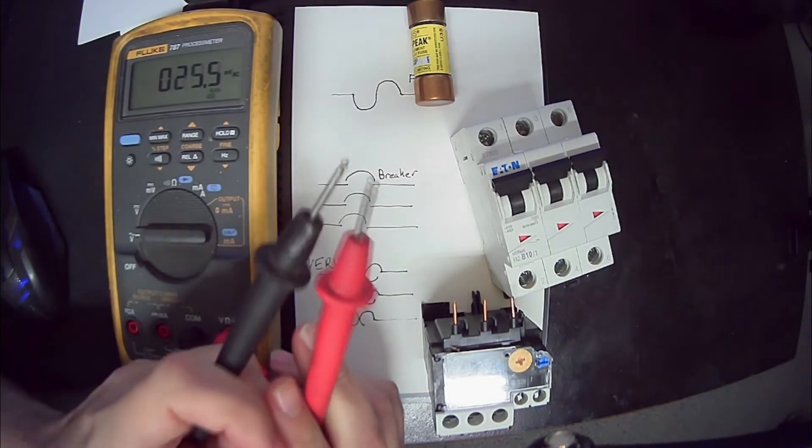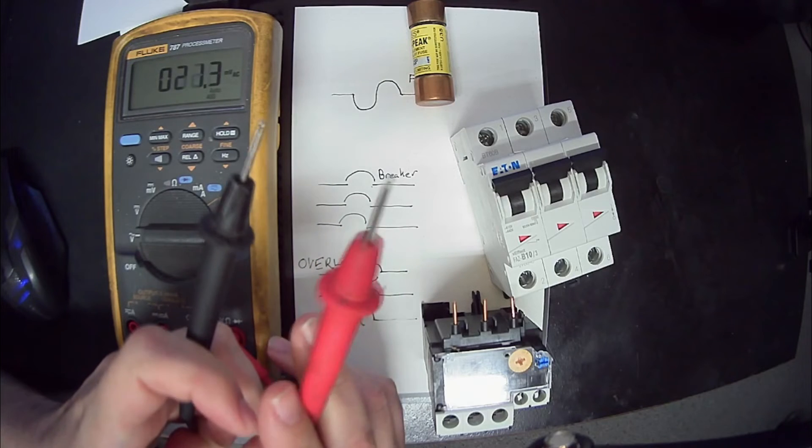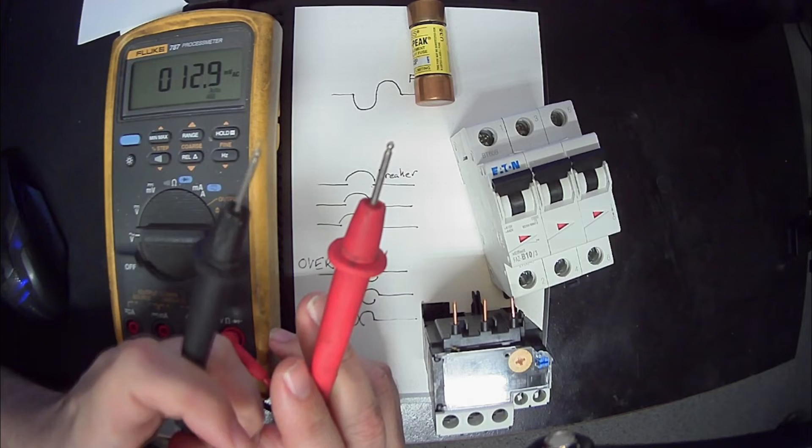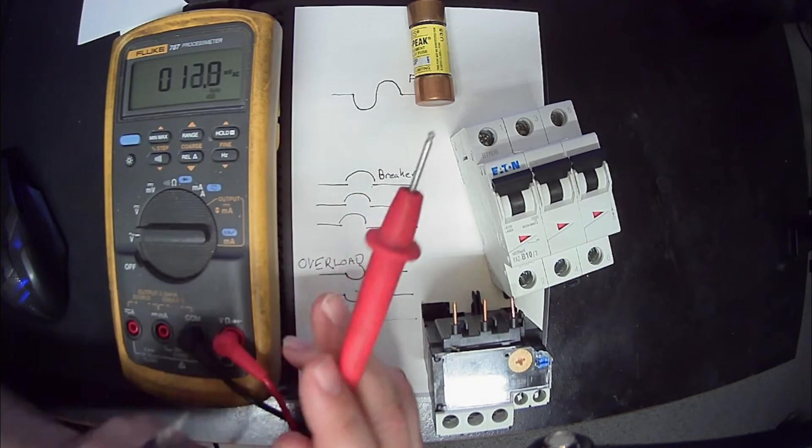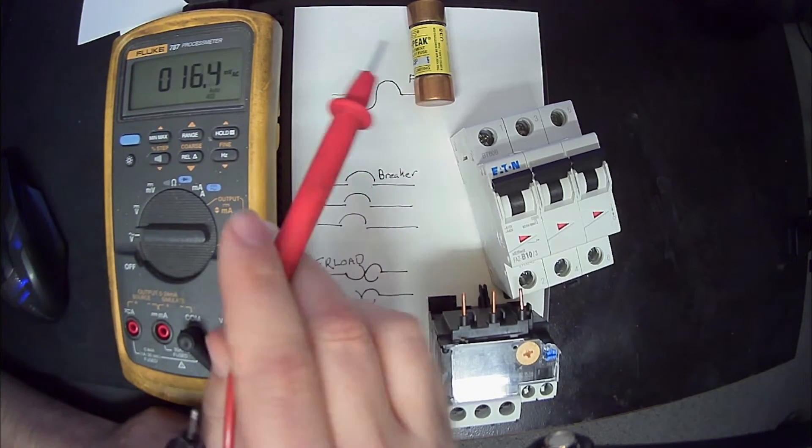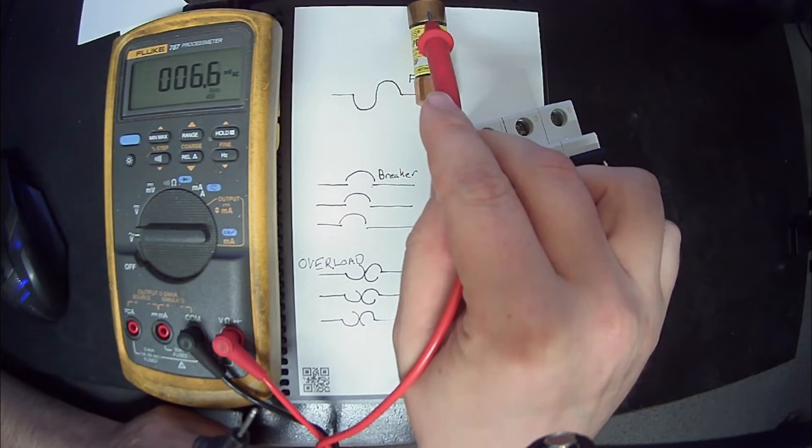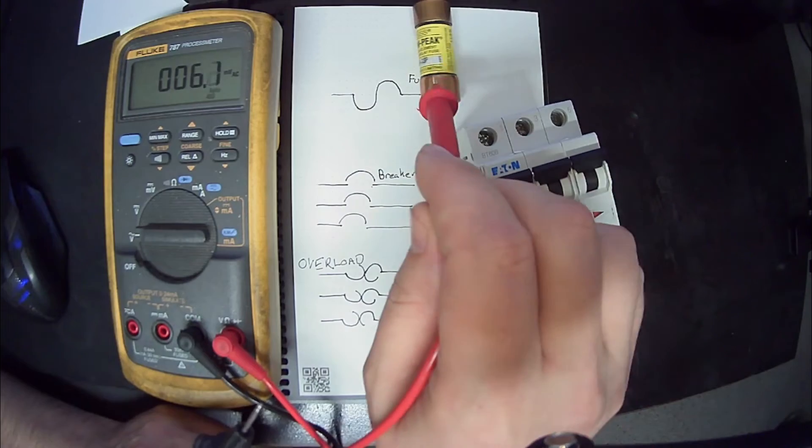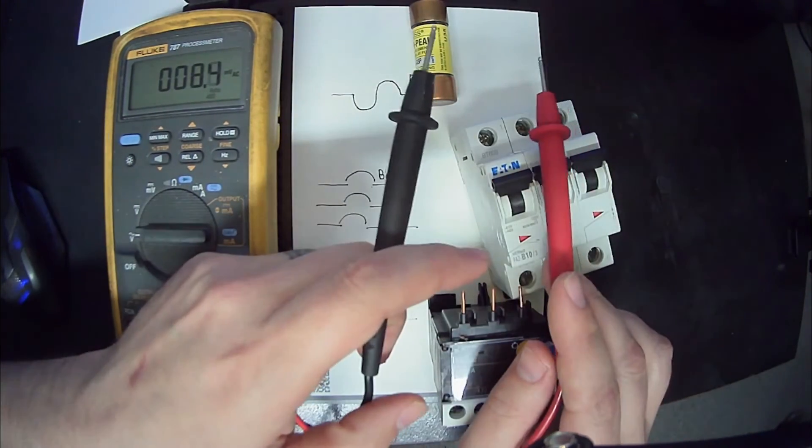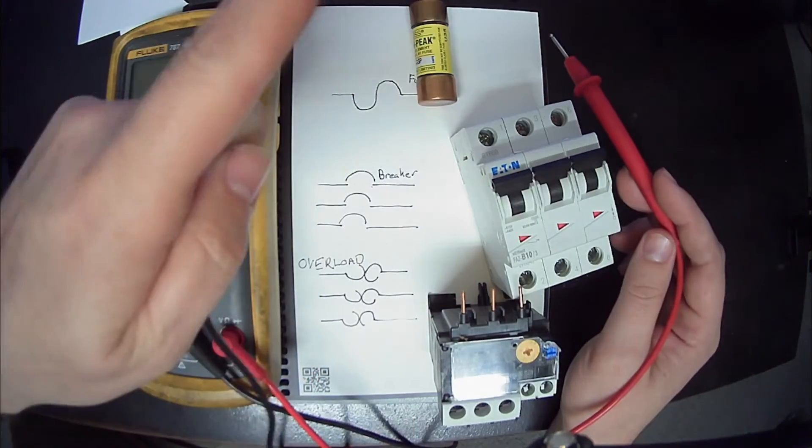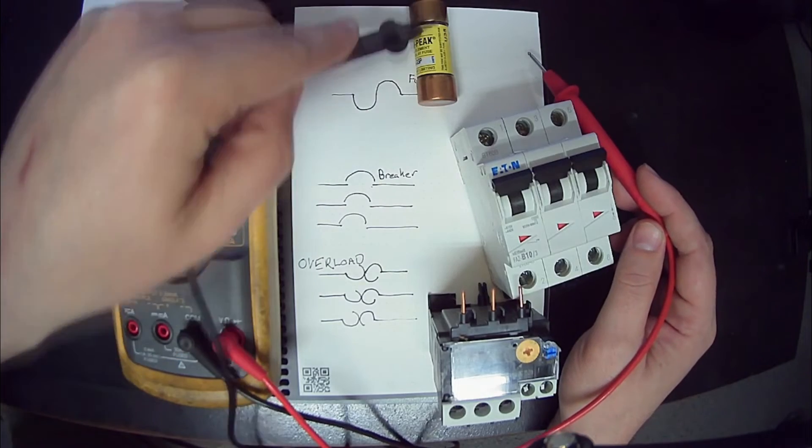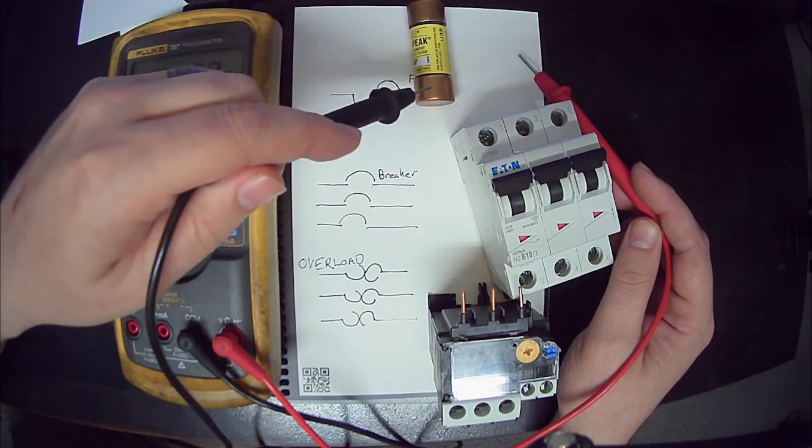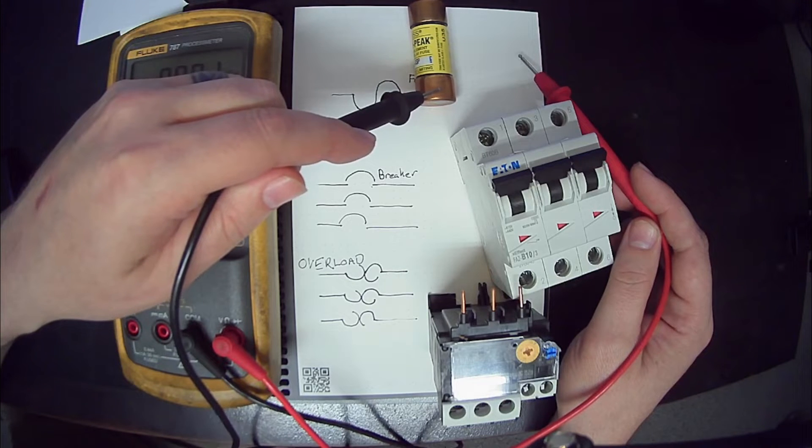With one meter lead, we're going to put it on reference and the other one on our test point, whatever it is that we're trying to test. If this fuse, for example, was being fed by a 120 volt system, then my reference is going to go on to neutral and I would just be testing this. I would look at the top and bottom and say okay, I've got 120 volts here and I've got 120 volts here. That would mean it's a good fuse.